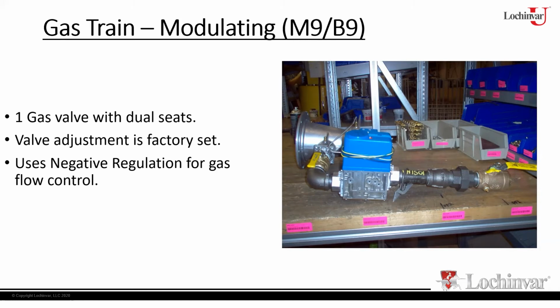The bias adjustment is at low fire. What the bias adjustment is doing is controlling the tension on the diaphragm. So remember, there's a diaphragm in the valve, and the suction from the blower, that vacuum that's created, lifts the diaphragm up. Well, the bias is controlling the tension on the diaphragm. So the more bias you put on it, the more tension you put on it, the more suction it takes to lift the diaphragm to get gas to flow. So we use this to control the low end, or basically your idling speed, if you will. So at the bottom end, we're controlling that side of it.